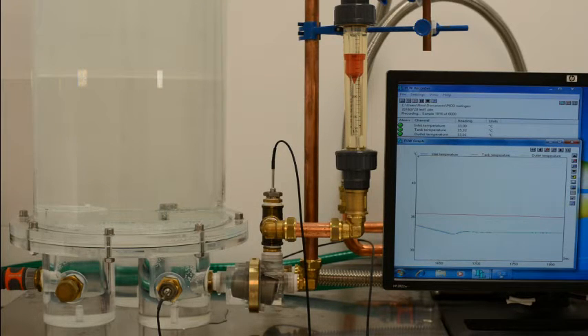And above the graph you can see the actual temperatures of the different sensors. So on top is the inlet temperature, which is 33.02 at the moment, the tank temperature, which is 35.31 at the moment, and the outlet temperature, which is 33.03 at the moment. So as you see, the temperatures of the inlet and the outlet are exactly the same at the moment. So the valve is 100% bypassing the flow. No flow is going through the tank at all.